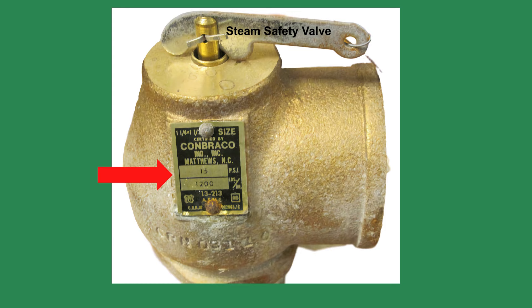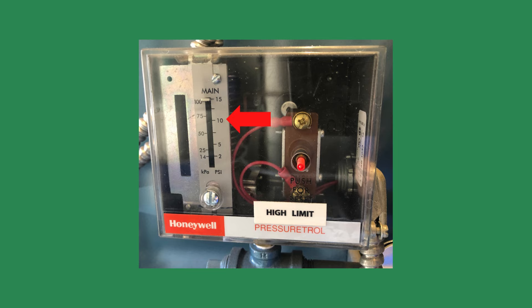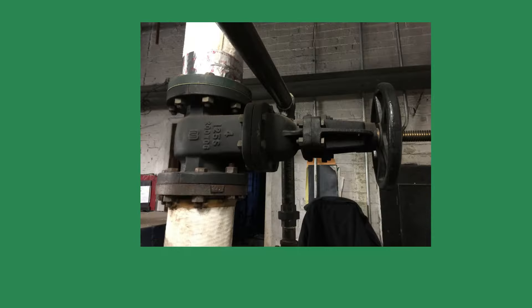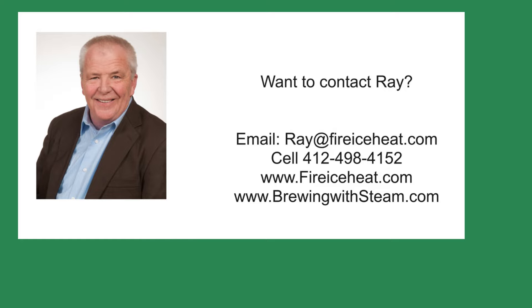I am skeptical of the accuracy at the far end of the range on the control. Plus, the boiler relief valve is set for 15 PSI, and I am a bit leery of going too close to that setting and causing it to open and lose all our steam. On a space heating application, I typically set the limit control for 10 PSI. When testing the boiler pressure controls, I prefer doing it when the system is offline. I shut the boiler isolation valve at the steam outlet — in this way, you can build up steam pressure inside the boiler alone. Once the controls are tested, you can open the valve and allow the steam into the system. If you do it while the pipes are filled with steam, the steam pressure may take a long time to drop.